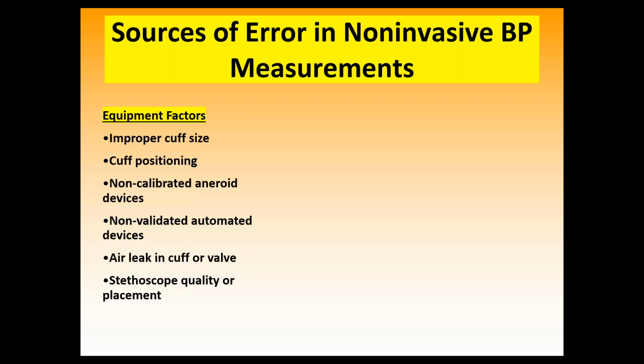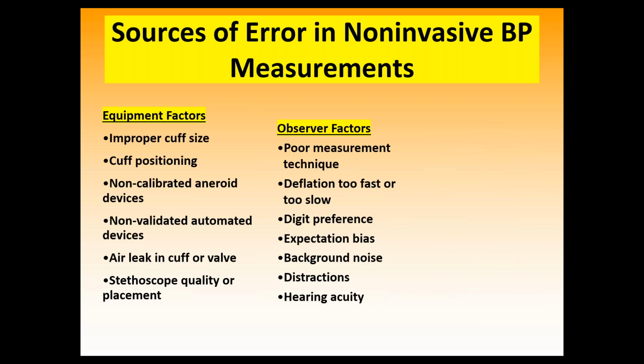You know, these aneroid gauges, you've seen how these things get banged around. They're thrown in drawers, they fall on the floor. They're getting all banged up, whacked out, and they can get out of calibration quite easily. Even the oscillometric devices, if they haven't been calibrated or validated properly, leaks, stethoscope quality, really cheap ones are going to have some filtering effects. Those Korotkoff sounds, which are pretty low frequency sounds, can be in the 20 to 40 hertz range. So any clinicians who have compromised low frequency hearing, you could in all likelihood be missing those sounds.